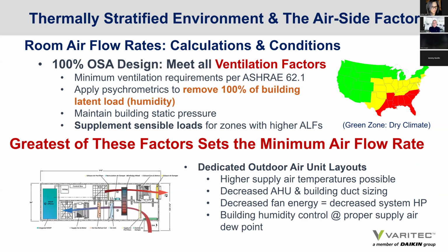First of all, you have to design the outside air to meet all the ventilation factors, minimum ventilation requirements per ASHRAE 62.1. The supply air of the 100% outside air unit needs to be supplied at a low enough dew point to absorb the humidity gain of that space, so that the space dew point will not exceed the chill water temperature serving the radiant devices.